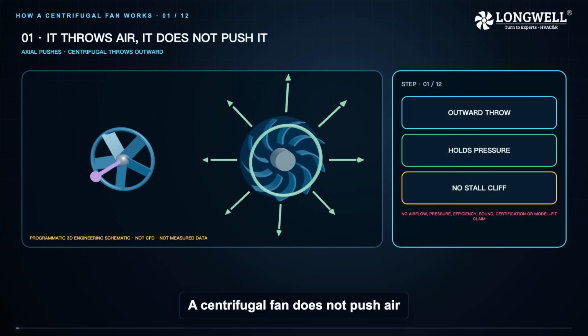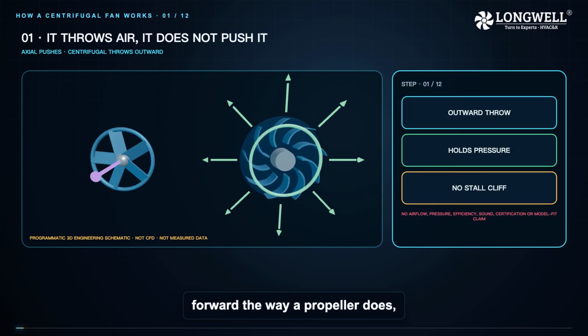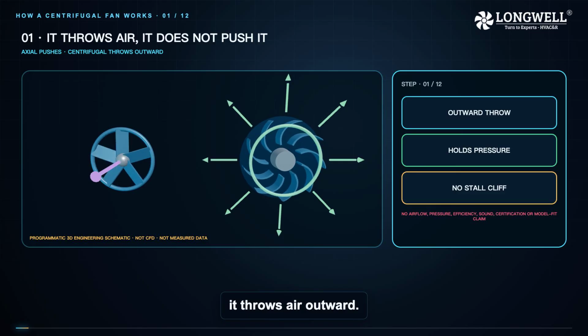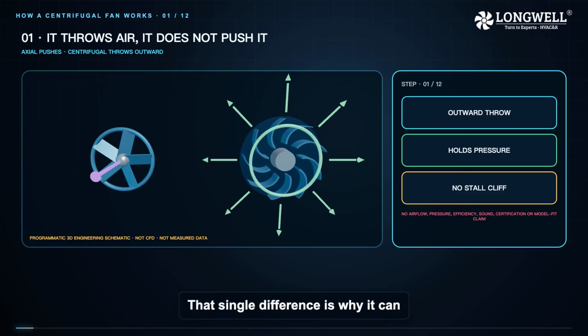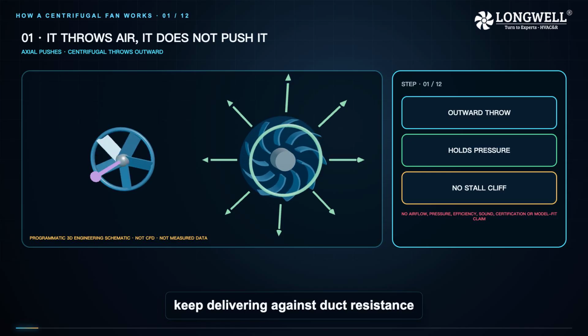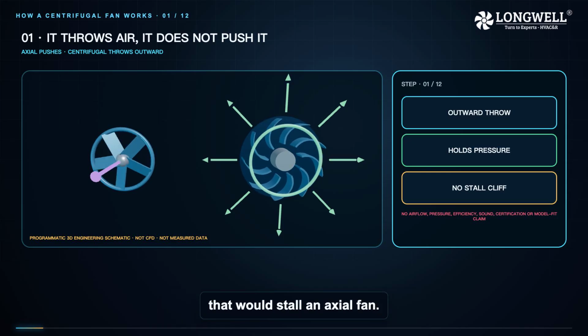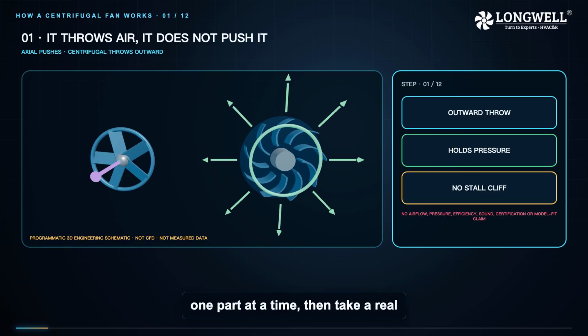A centrifugal fan does not push air forward the way a propeller does, it throws air outward. That single difference is why it can keep delivering against duct resistance that would stall an axial fan. We are going to build this machine one part at a time, then take a real one apart.